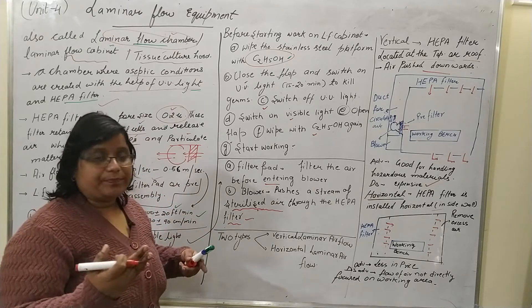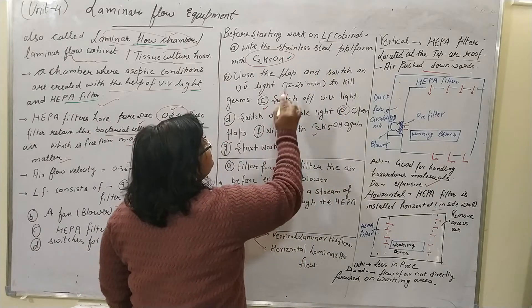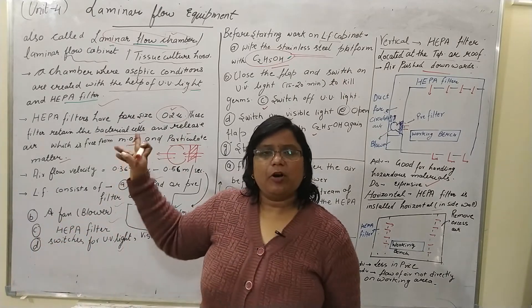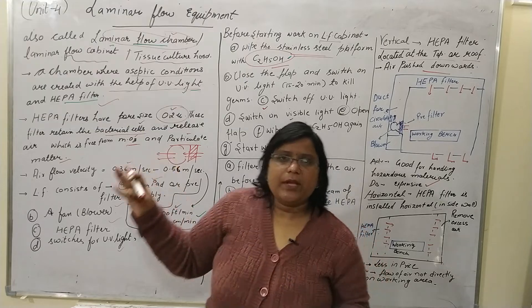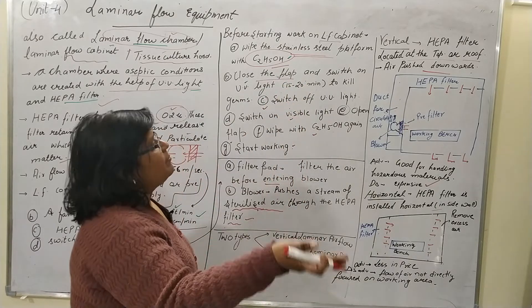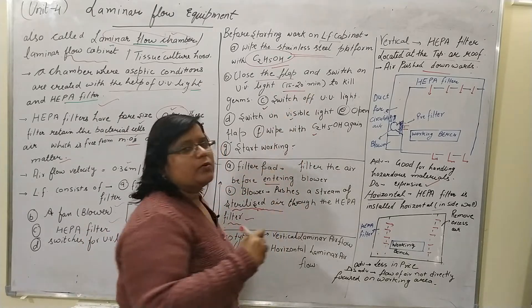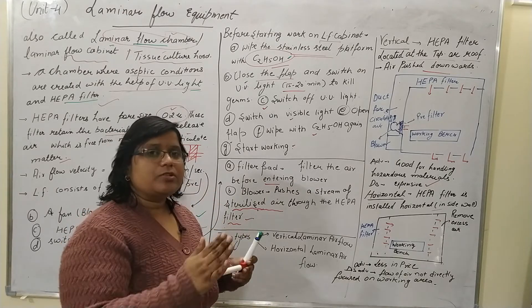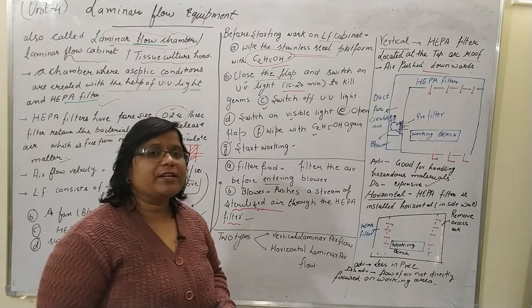Before starting work on the laminar airflow cabinet, first wipe the stainless steel platform with ethyl alcohol. You can see the diagram of the laminar airflow — it shows the stainless steel bench, HEPA filter, switches, and all components. After wiping, close the flap and switch on the UV light. The switch for UV light is located outside the chamber, and when you switch on the UV light, you should stay far away from the laminar airflow, because UV light is quite carcinogenic.